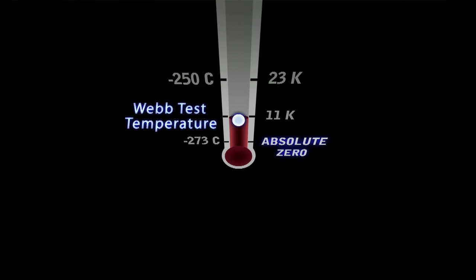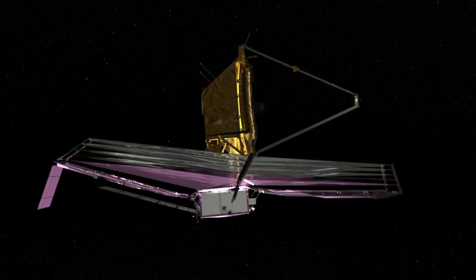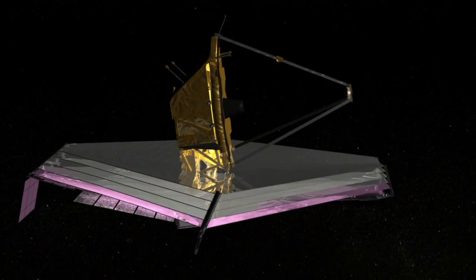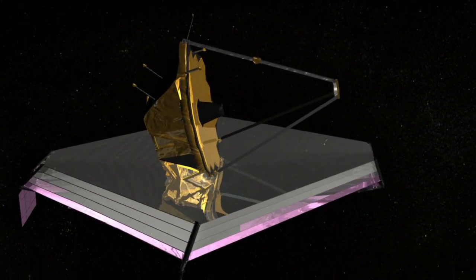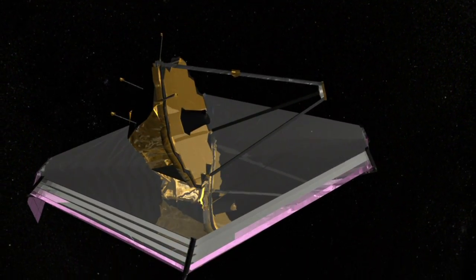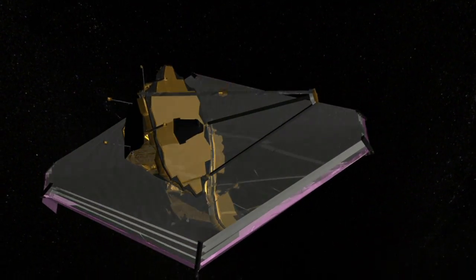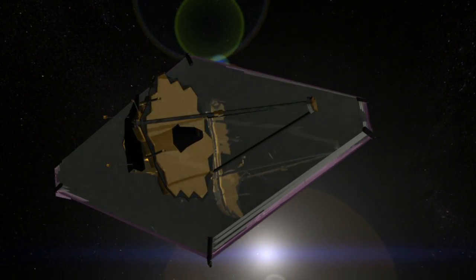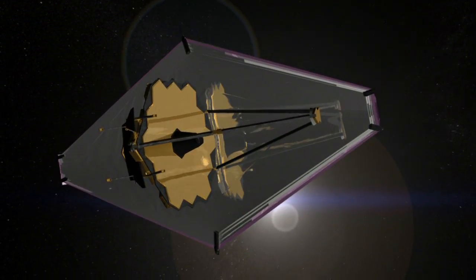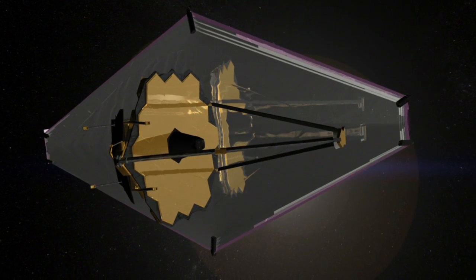What we get out of a thermal vacuum chamber test is that we can evaluate whether or not the spacecraft, all its systems, perform like they're supposed to perform once they're out into space.